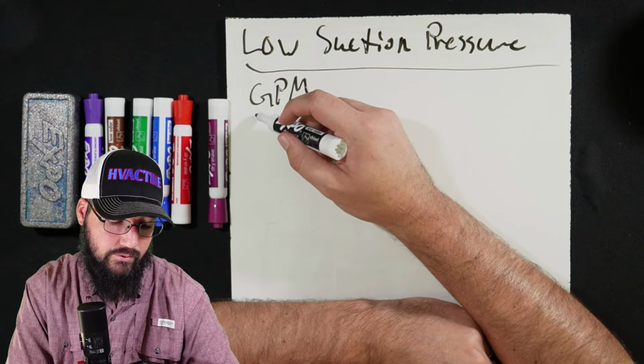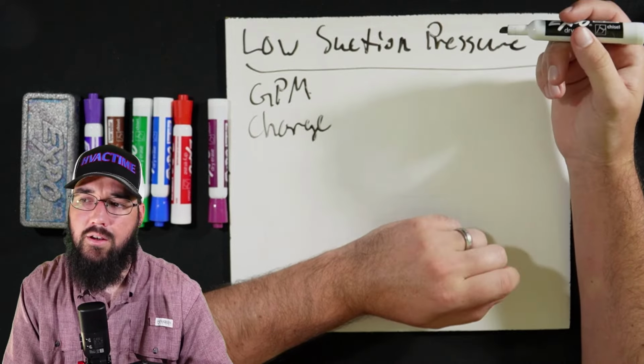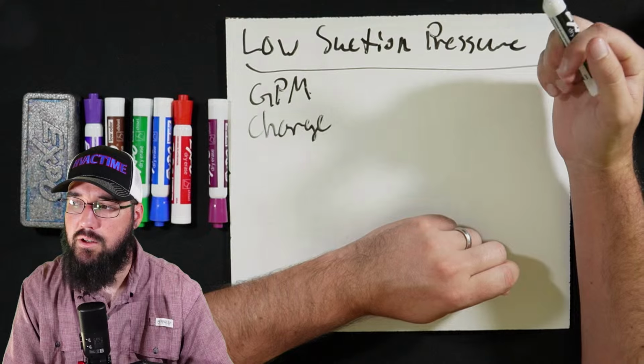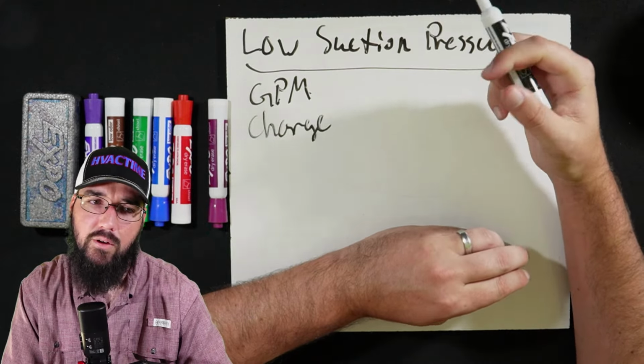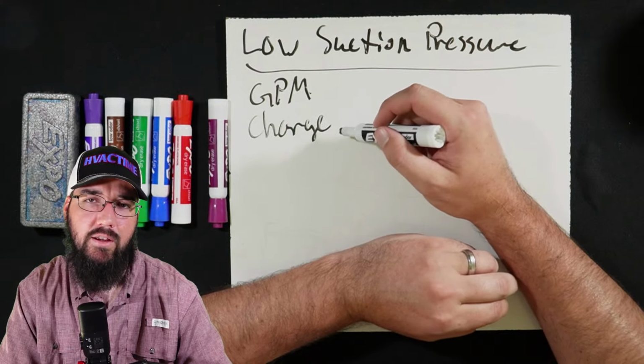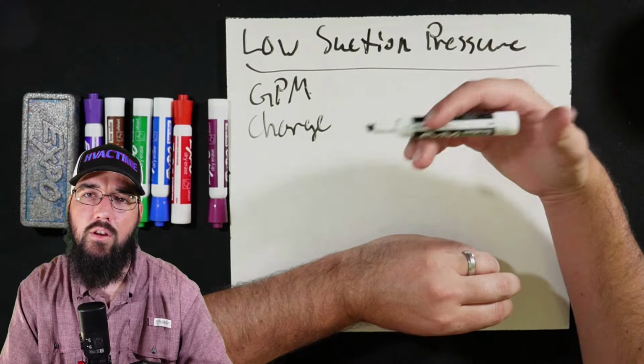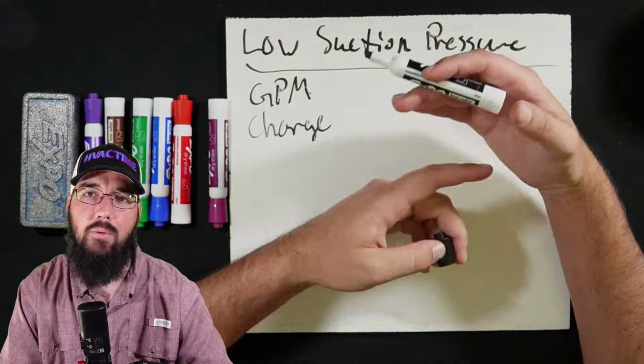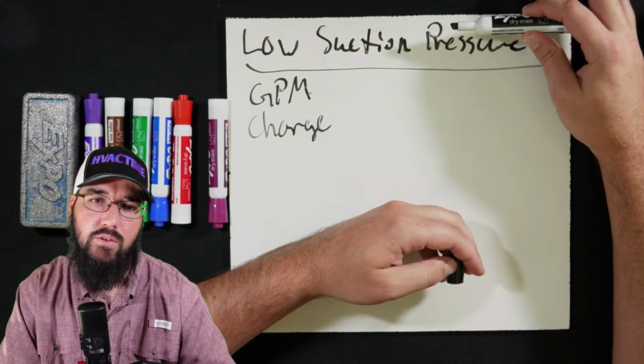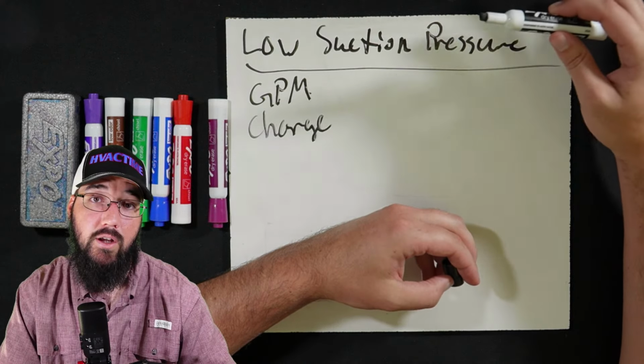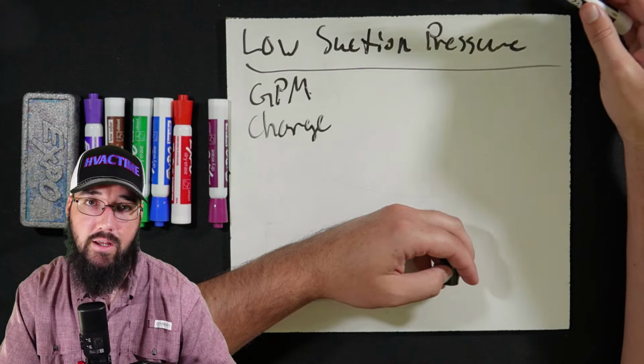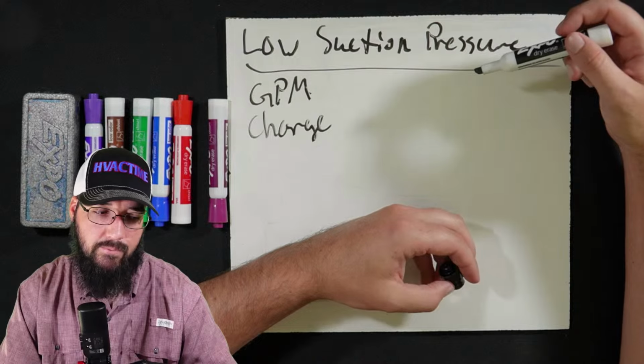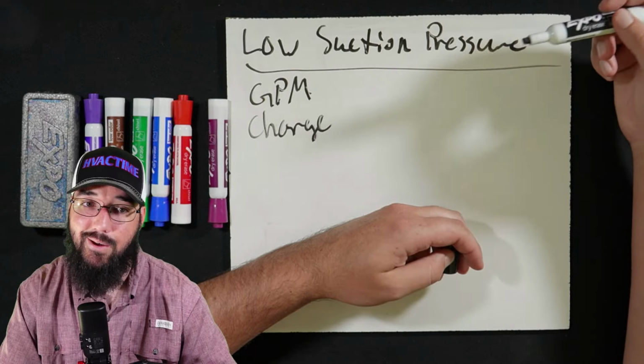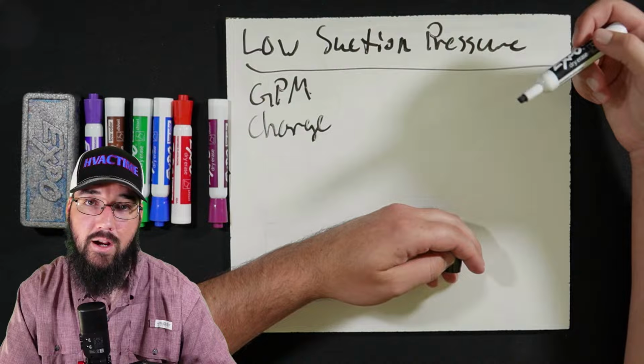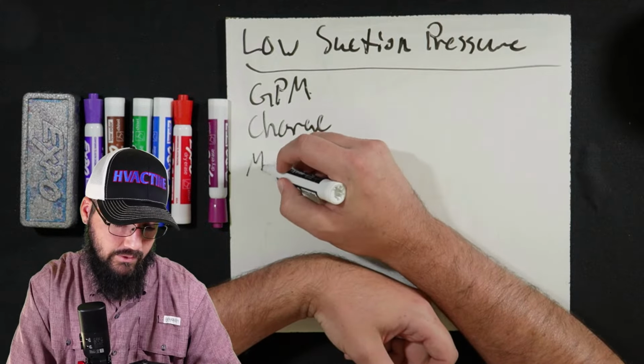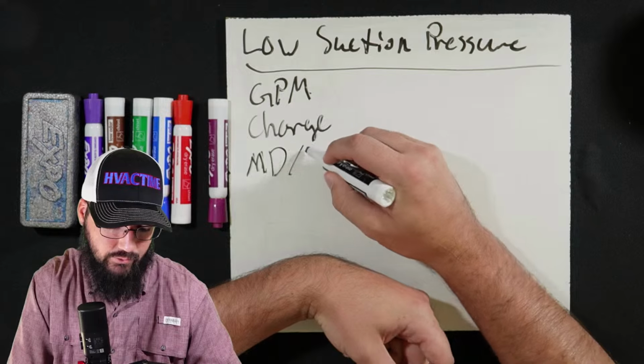It could also be a charge issue. These machines, I believe, run around 12 degrees or so of subcooling at load. So check what your subcooling is with a load on the machine. That will give you an indication if you are seeing low suction pressure but also a really low subcooling. That could be a very quick indication that we may have a charge issue here. If your subcooling is good or high, then it may not be charge. It could be the dryer or metering device. So I'm going to say MD for metering device or dryer issue.